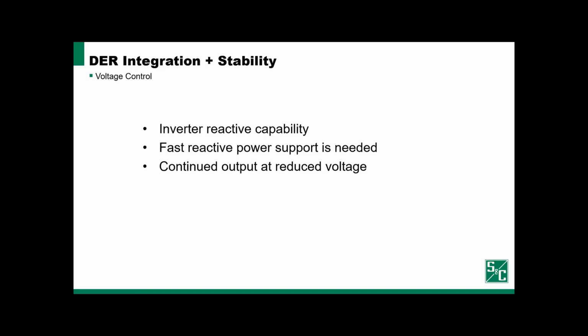It's important as inverters displace rotating machines that we have reactive capability in our inverters to supply the reactive power needs of our power system and ensure that we're meeting the system needs here. It's also important that that reactive power support comes very rapidly. When there's a system event, reactive power needs to be supplied very rapidly to maintain system voltage, which plays into the last point here. It's important that resources are capable of continued output at reduced voltage.